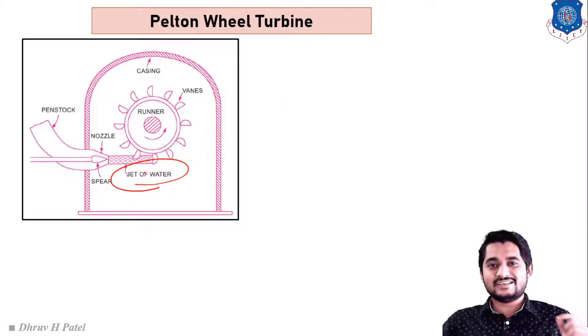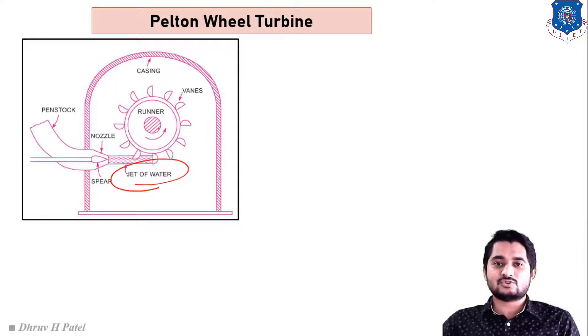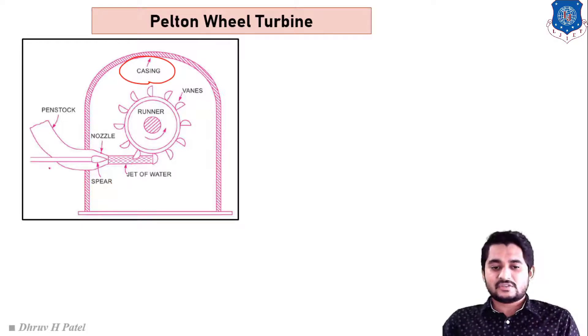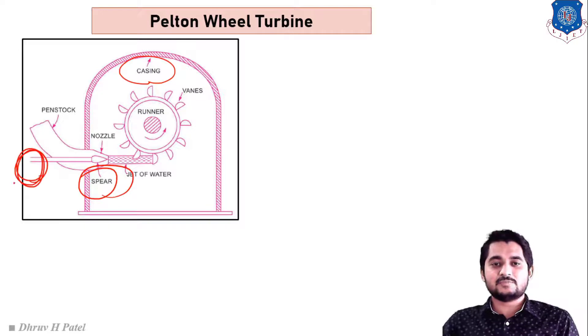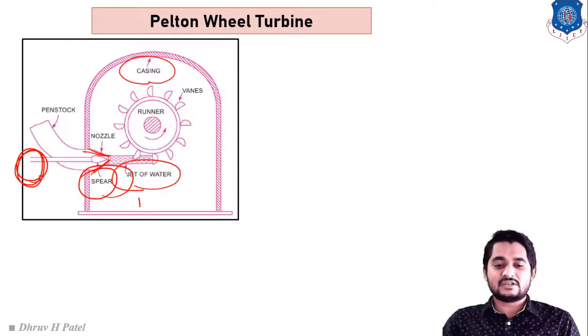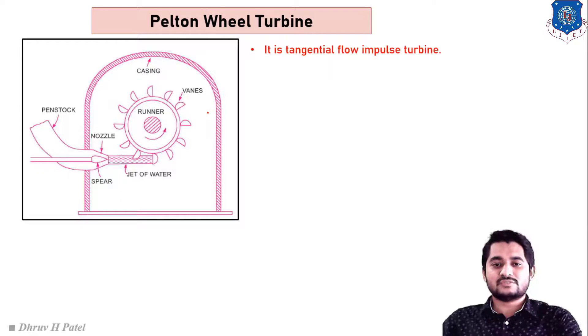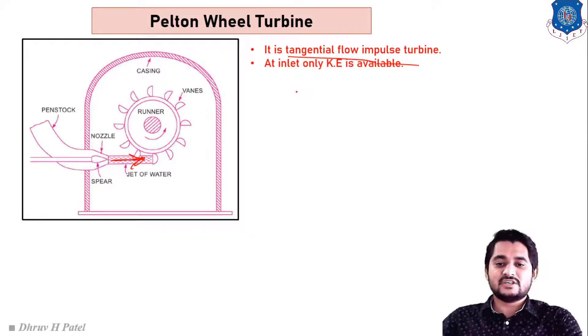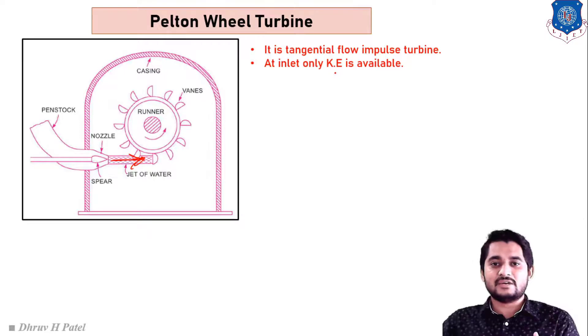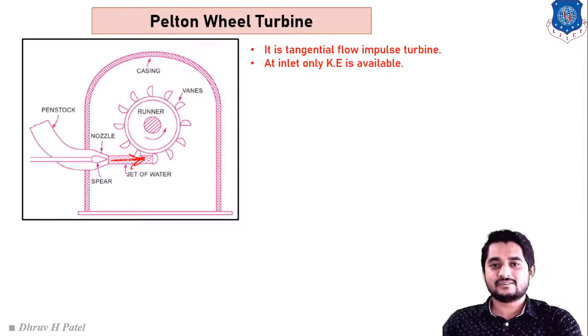From the nozzle, a jet of water attacks on the blades of the turbine and the turbine rotates with respect to its center. Casing is used for safety purposes. A spear regulates the inlet water quantity — by rotating the spear in any direction we can regulate the kinetic energy at the turbine inlet. From the sketch, the Pelton wheel turbine is a tangential flow impulse turbine, meaning water attacks in the tangential direction to the blade, and only kinetic energy is available at the inlet.